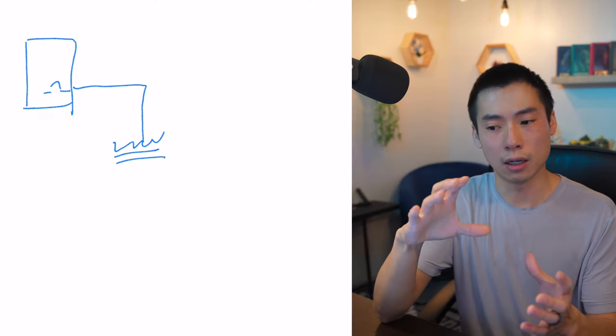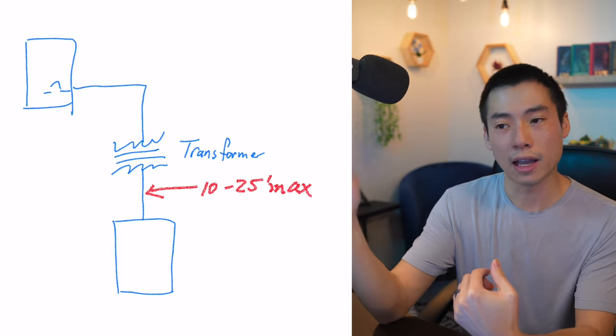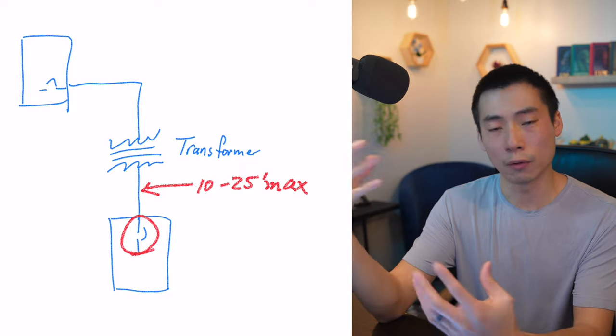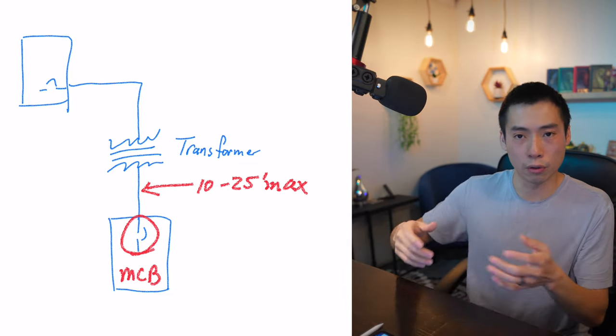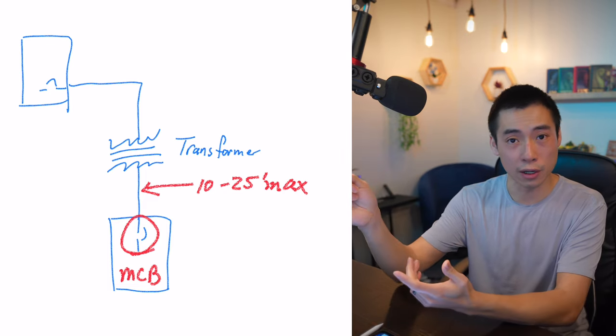Anything within 10 to 25 feet on the secondary side of a transformer needs to have some type of overcurrent protection. So usually you would put an MCB panel on the secondary side and that breaker acts as your protection.